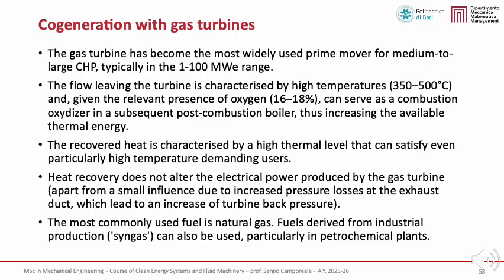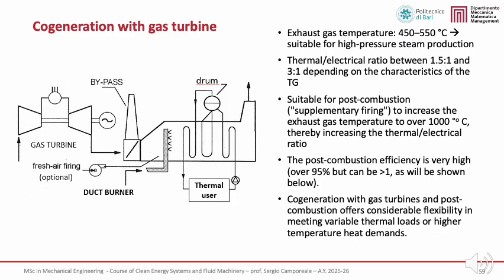As a result, the recovered heat is available at a high thermal level, making gas turbine cogeneration suitable for high-temperature applications such as industrial processes or steam production. Now, we analyze cogeneration systems based on gas turbines, focusing on the schematic layout and on the role of post-combustion, also referred to as supplementary firing. Starting from the left side of the diagram, the gas turbine converts the chemical energy of the fuel into electrical power, which is delivered through the generator.